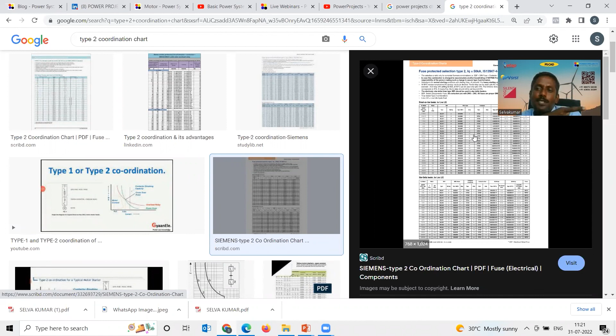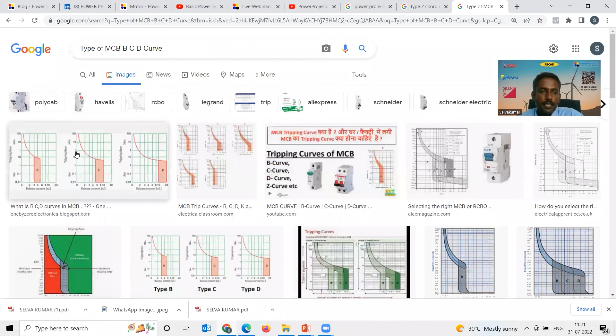When choosing an MCB, you have to be clear about what MCB you are selecting. There are at least 3 common types. This image gives what is type B, what is type C, what is type D, what is overload, what is short circuit protection, and where to use each. So you have to be clear about what applications need what type of MCB.